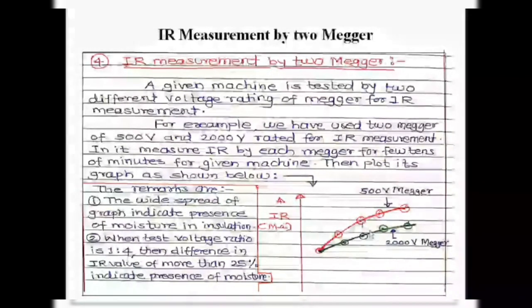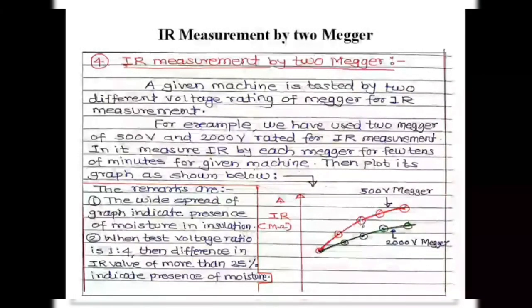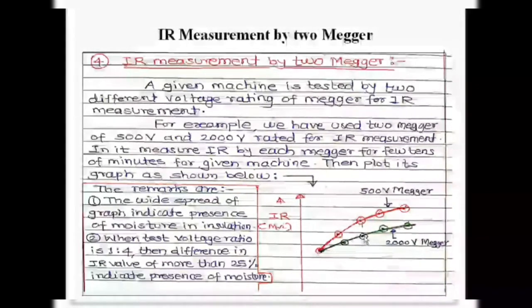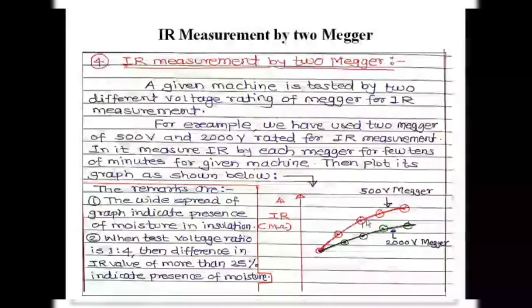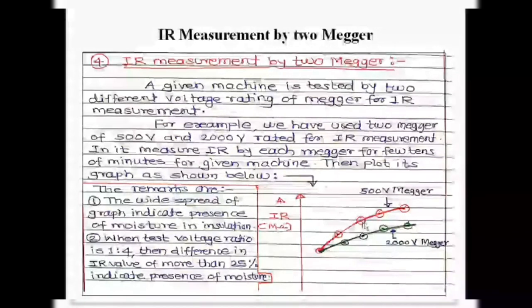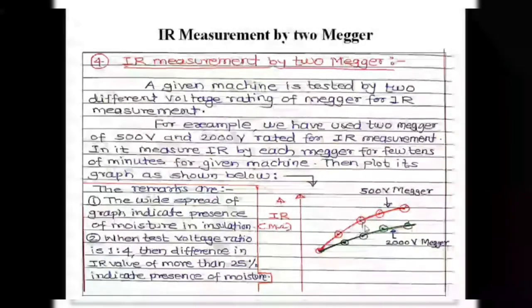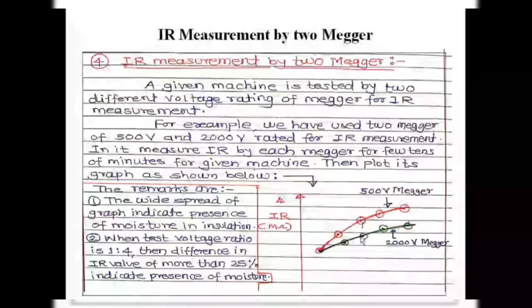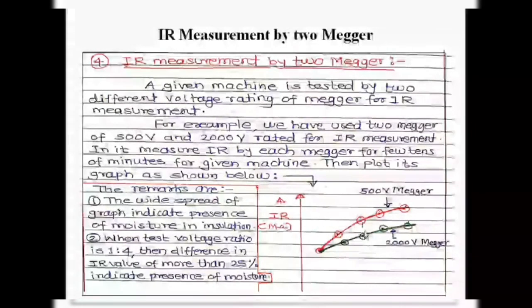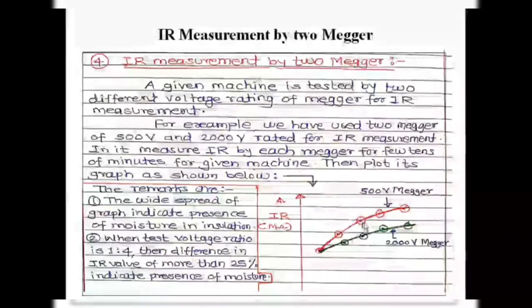The second interpretation from this graph involves comparing readings of the 500 V and 2000 V meggers at the same time duration. The voltage rating ratio of these meggers is 1:4. If the IR value from the 500 V megger reading differs by more than 25 percent from that of the 2000 V megger for the same time duration, it indicates the insulation has absorbed moisture and has solid impurities, requiring reconditioning to improve the IR value of the given electrical equipment.